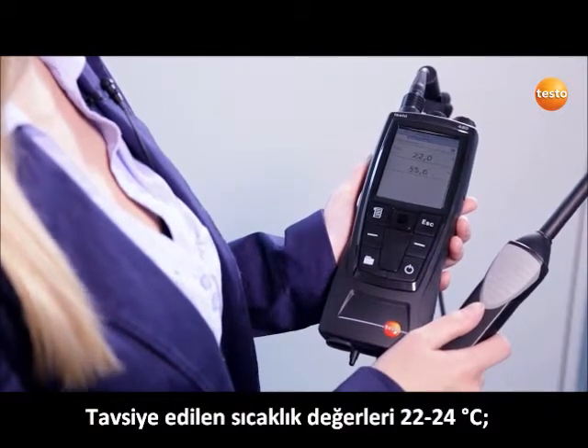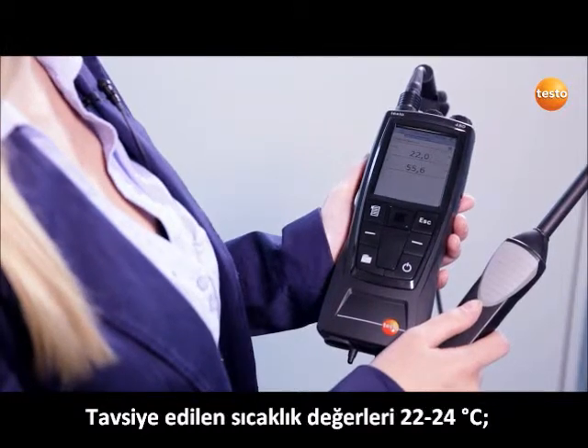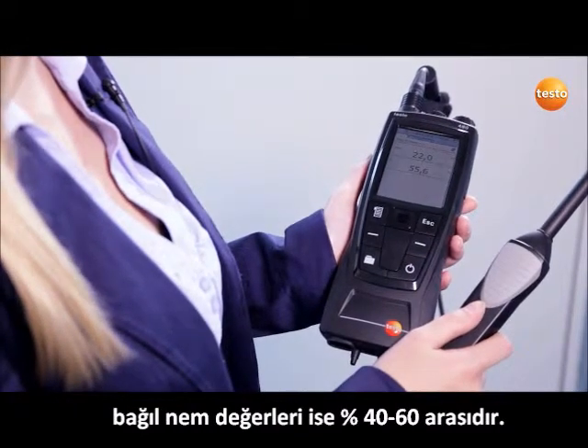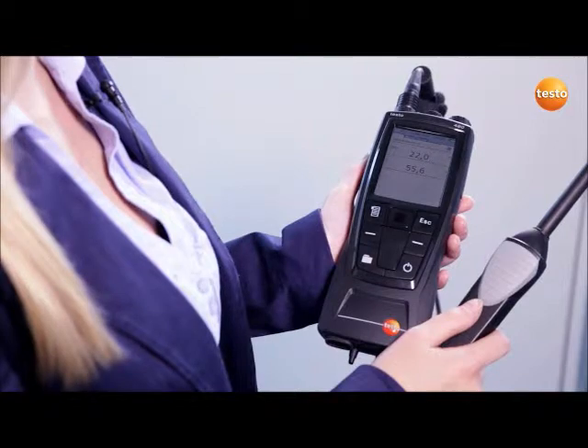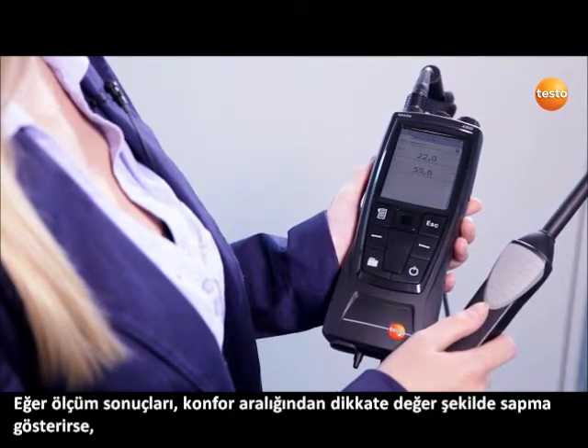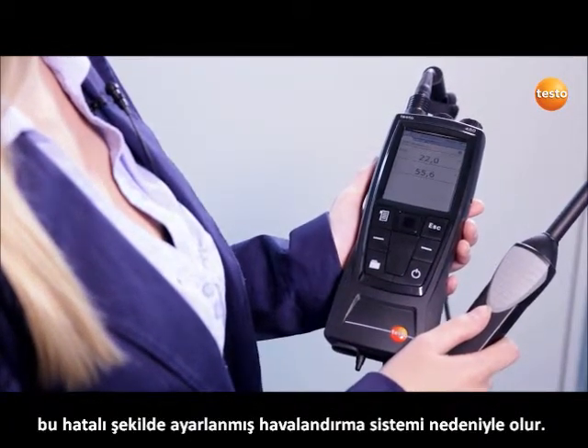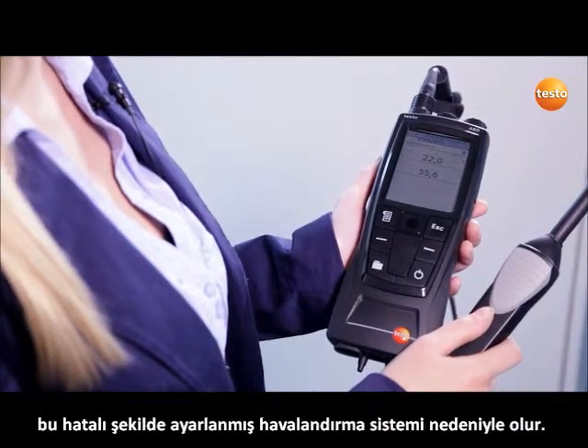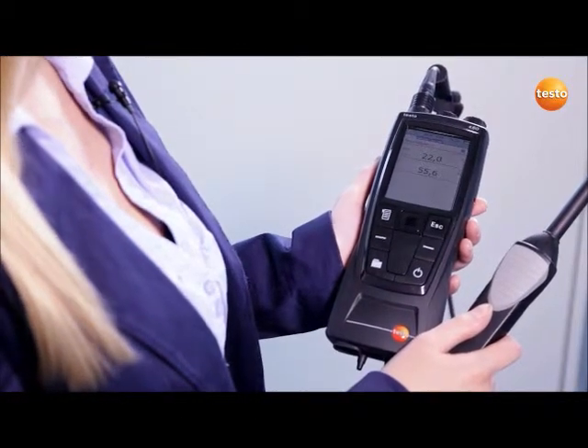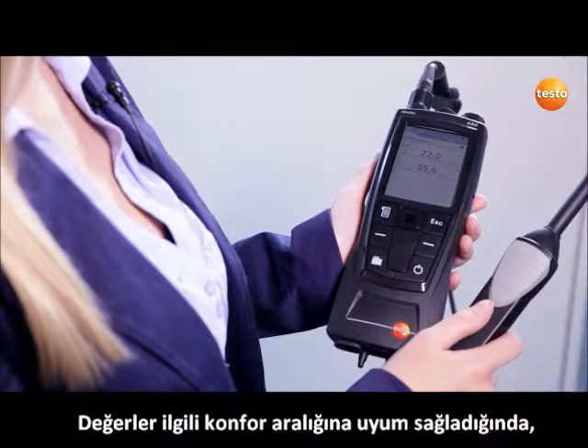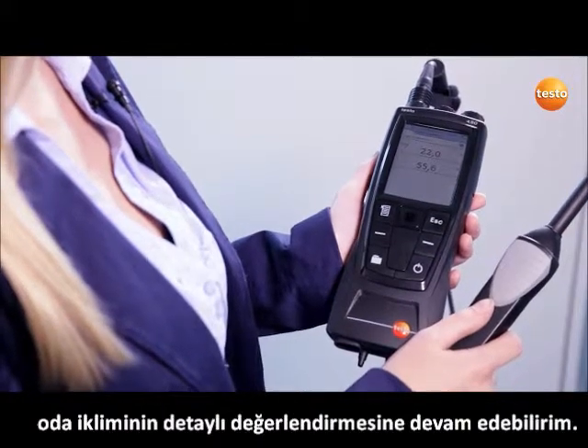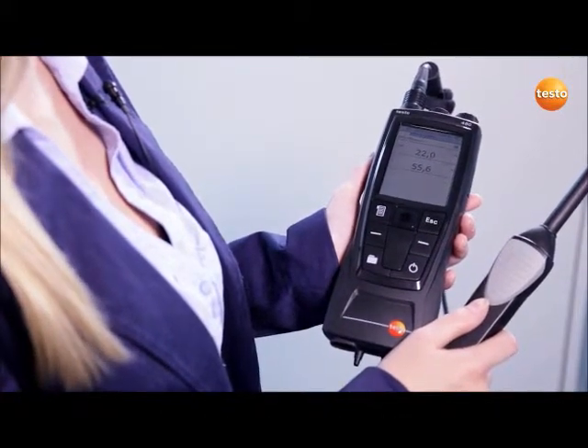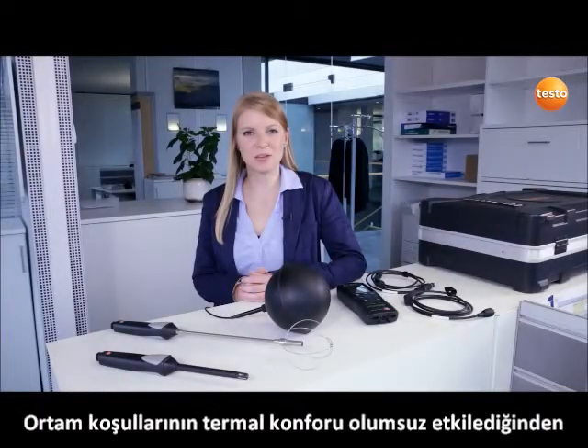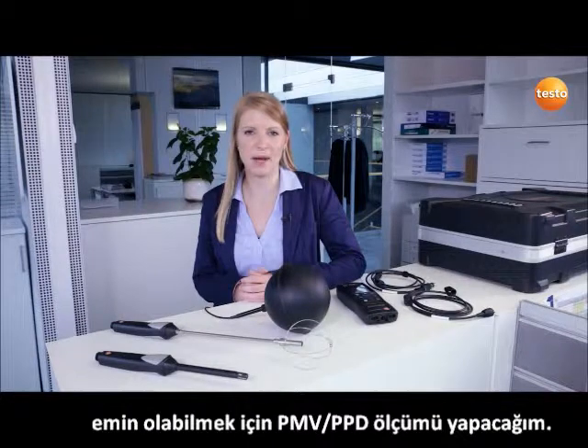The recommended values for offices are between 22 and 24 degrees centigrade and 40 to 60% humidity. If the measured values here already showed a considerable deviation from the comfort range, this would be due to an incorrectly adjusted ventilation system. Since the values correspond to the respective comfort ranges, I can continue with a detailed evaluation of the room climate. In order to be able to judge whether the ambient conditions are actually causing the thermal discomfort, I'll now conduct a PMV/PPD measurement.